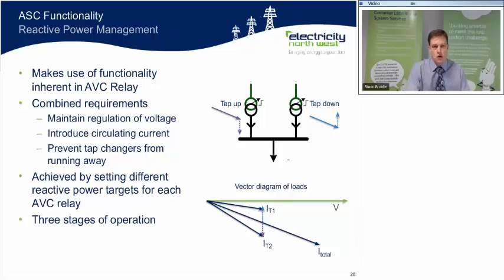So looking at the reactive power and the tap stagger principle for managing the voltage, this makes use of some of the functionality of the AVC relay. It's not as simple as just tapping up one relay and tapping down the other relay. We need to maintain voltage regulation and also prevent the tap change from running away.